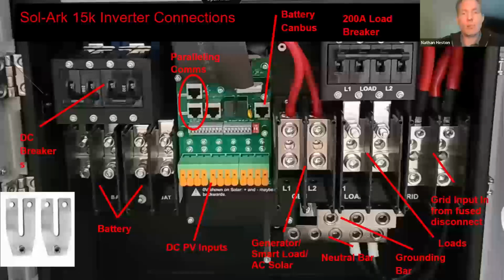In the center of the screen, this is where the communications is. The paralleling communicating RJ45 connections are shown there with a circle. And so if you have multiple inverters, you're going to daisy chain them. One's an input, one's an output, and this runs in a big loop. So if you had 2 inverters paralleled, you'd fill both of those spots with Ethernet cable to run between them. The battery CAN bus is on the right side of the control board there. That is going to run into your battery bank. You only need 1 CAN bus connection to the inverter for your battery loop.